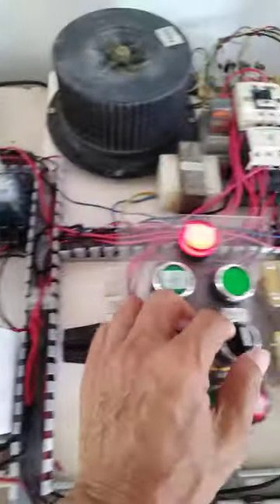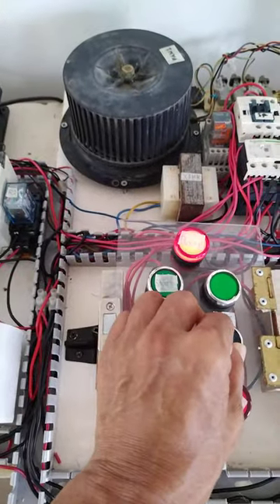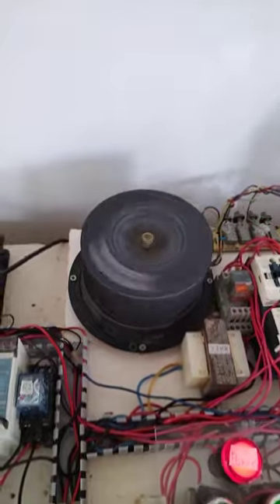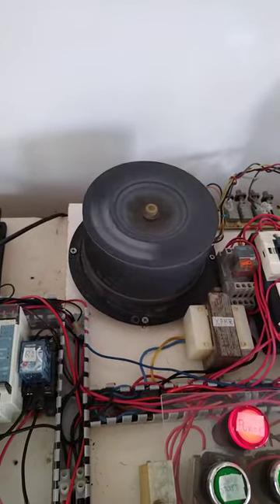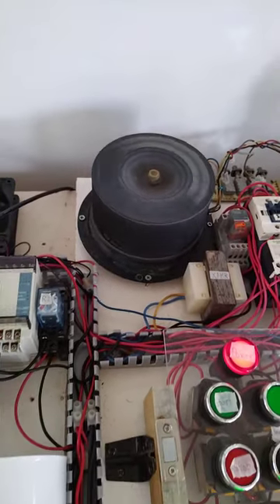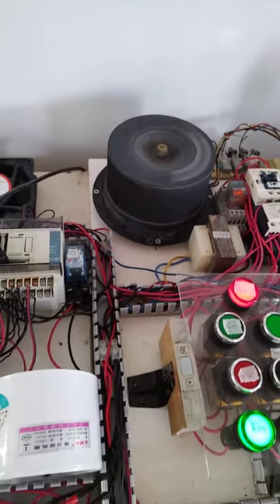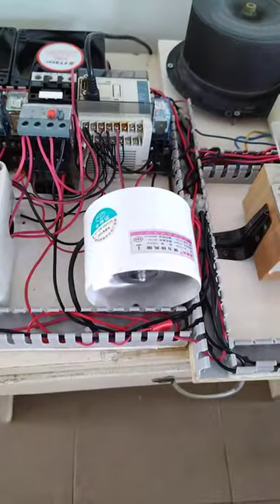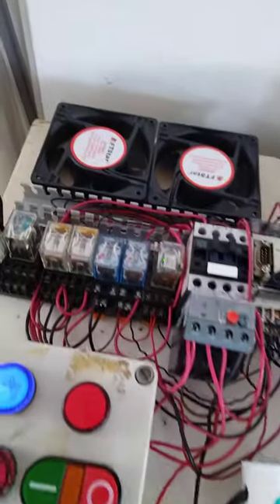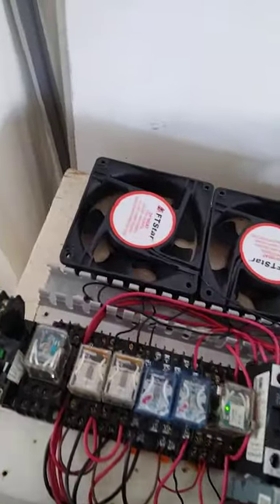So let me test this one. I will put both the selector switches in automatic, then we will see how it will start. Immediately one fan starts, then we will count five seconds. Five seconds. Then another fan here will run.